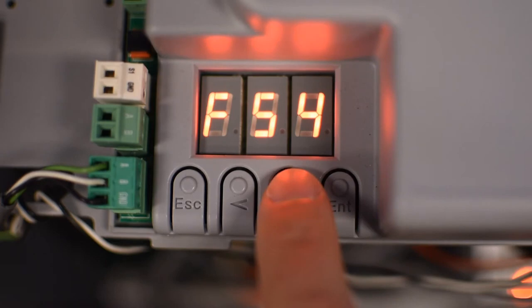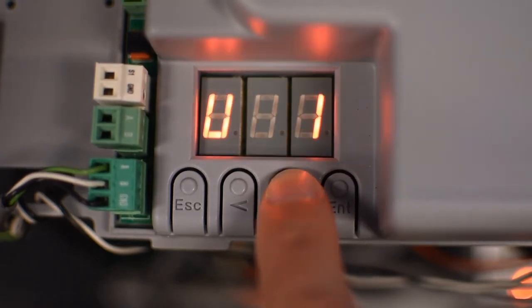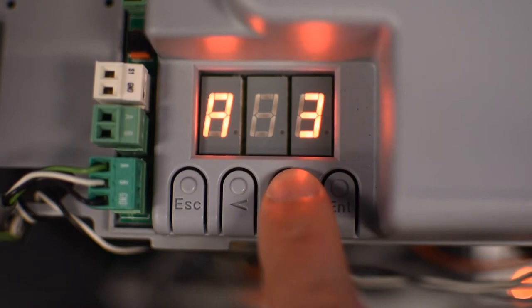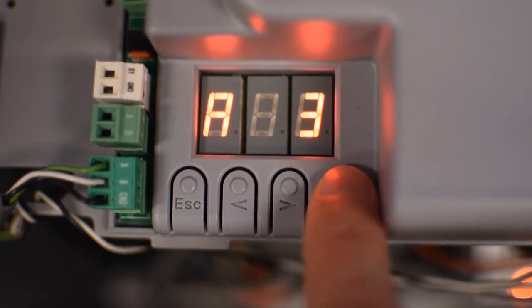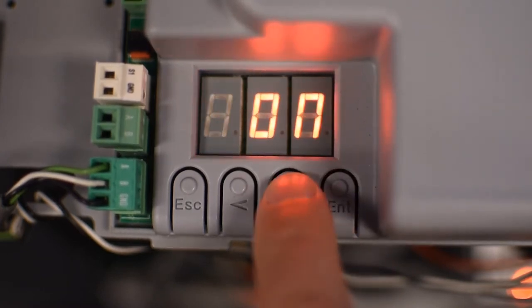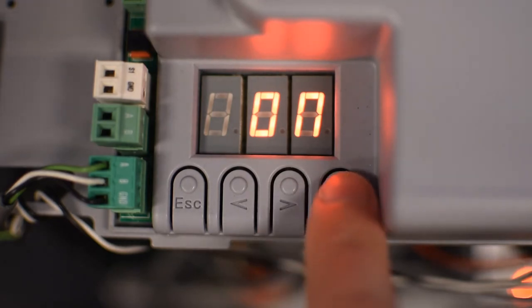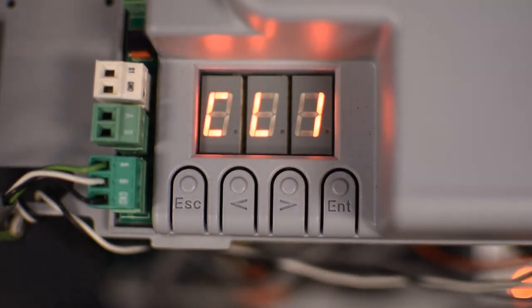Now we're ready to calibrate the encoder in A3. Press Enter and use the arrows until you see On, and press Enter. It will start the calibration procedure by closing and then opening.